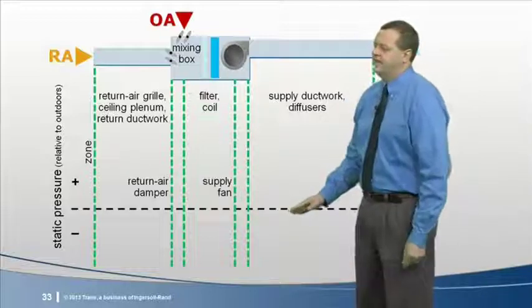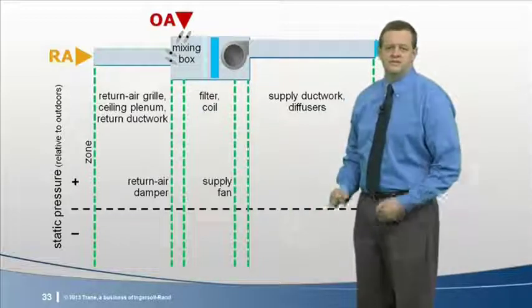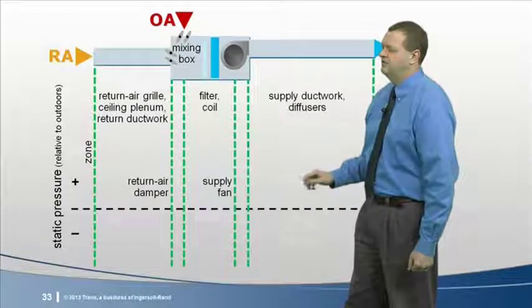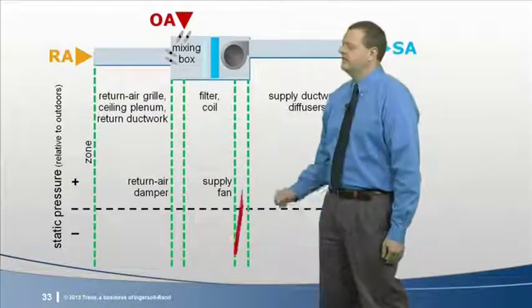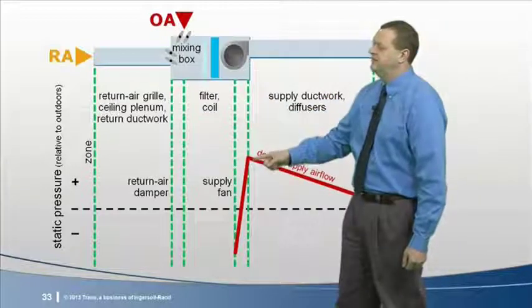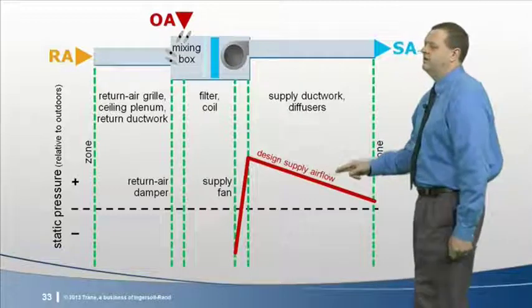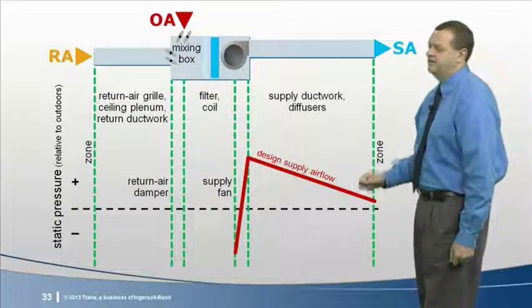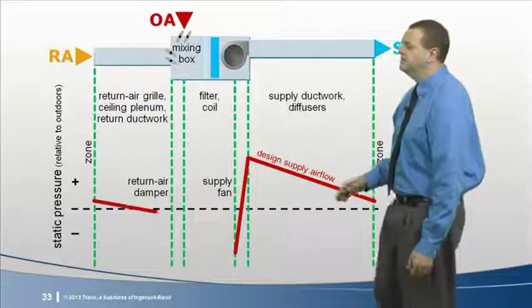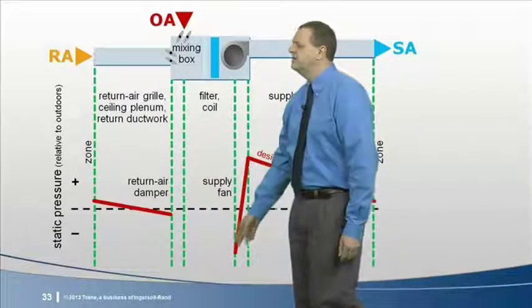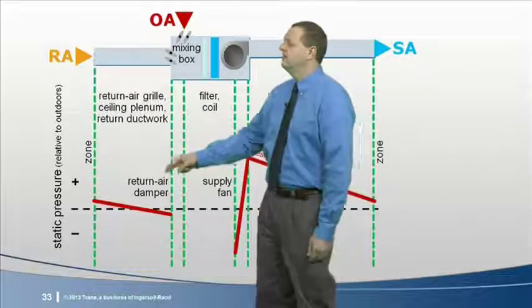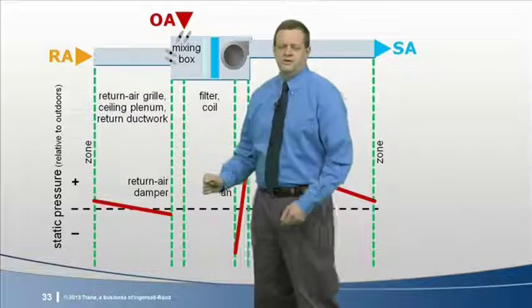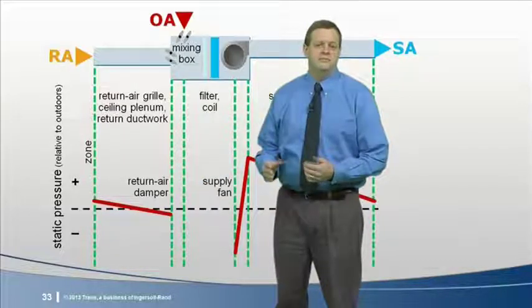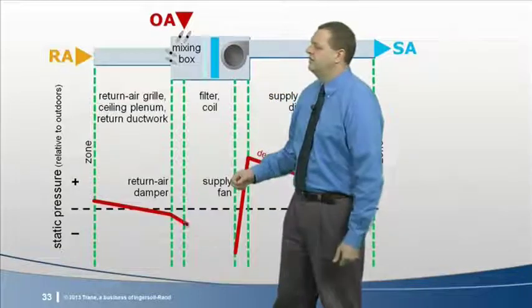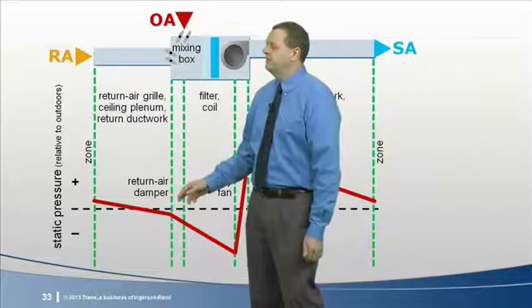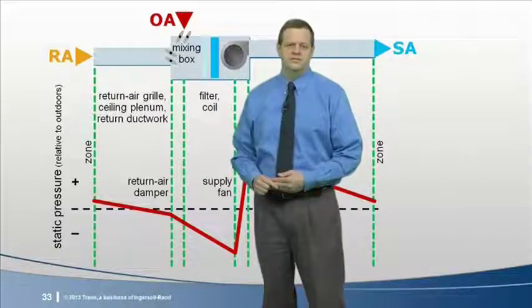This accompanying chart depicts the static pressure as air moves through the various components of the system. Positive pressure above this dashed line and negative pressure below it. Now the supply fan must create a high enough pressure at its discharge to overcome the pressure losses associated with pushing the air through the supply ductwork and diffusers and into the zone. In addition, the fan must create a low enough pressure at its inlet to overcome pressure losses associated with drawing the air out of the zone and through the return air path, which might include a return grill, ceiling plenum, and maybe some ductwork. And then to draw the air through the return air damper, filters, and coils inside the air handler or rooftop unit.